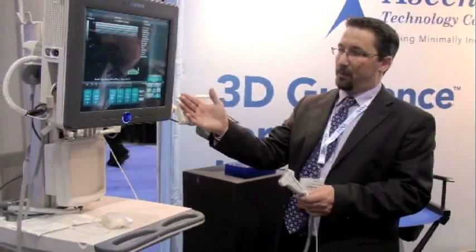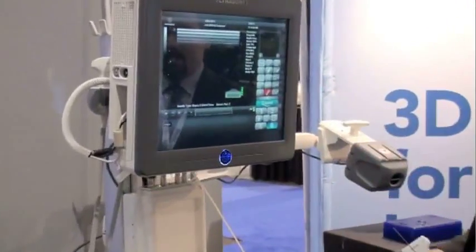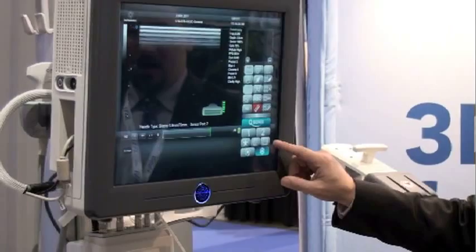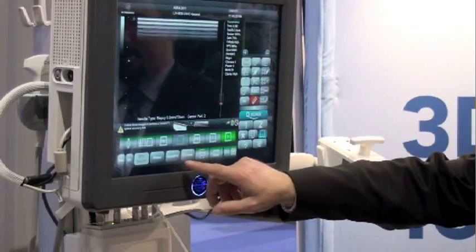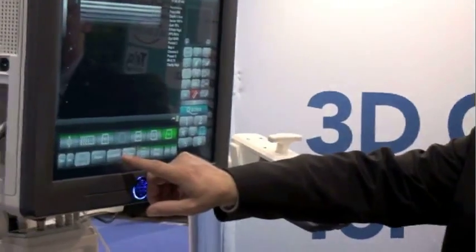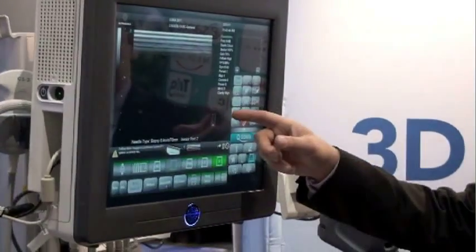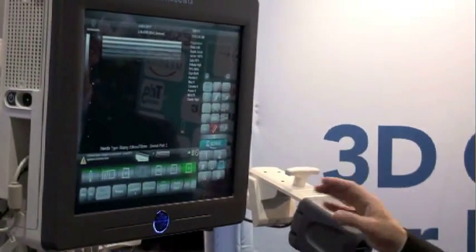I'll explain how to get the system started so you can get it up and running. On the main screen of the ultrasound system, there's a control on the side for imaging modes. At the bottom of the screen, you'll see a button labeled SonixGPS. To turn the GPS system on, tap the button once, and on the main image you'll see a signal bar with five segments, indicating that GPS is enabled and showing the relative signal strength between the sensors and the transmitter.